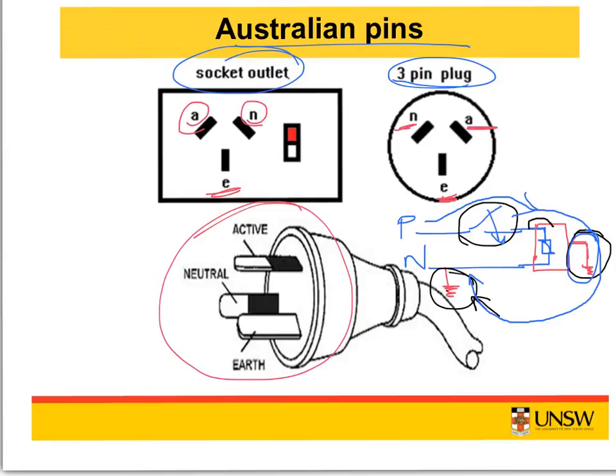So if we swap the neutral and the phase, what happens? Let's take that scenario. So here we have the neutral point which is actually earthed. Let's say we swap the neutral and the phase, therefore the neutral gets connected through the switch. So we have the same circuit here, and then let's say this is the phase. We are swapping the phase and neutral for the load. So this has an ECP again, and the ECP is grounded.